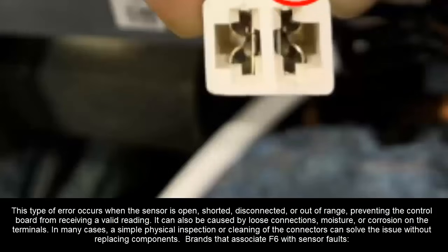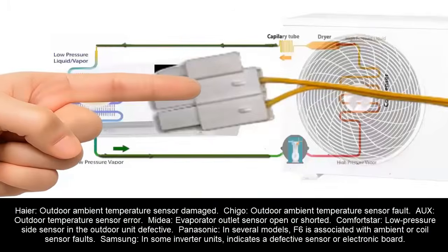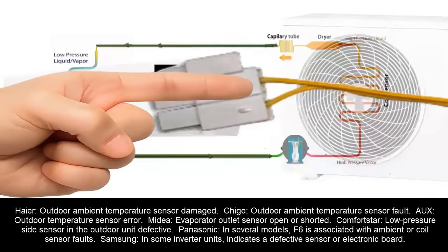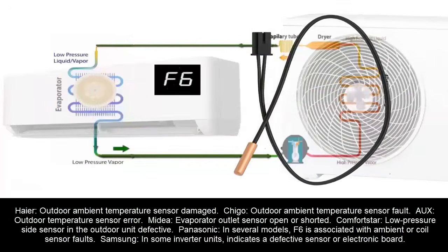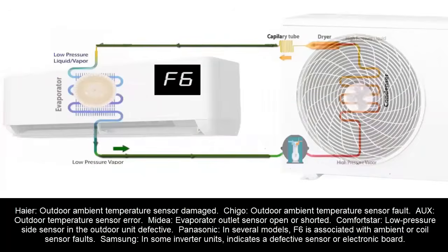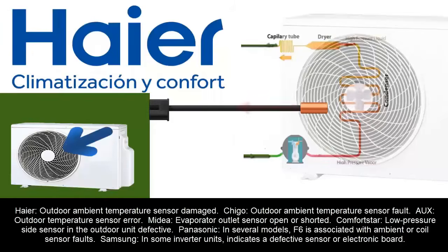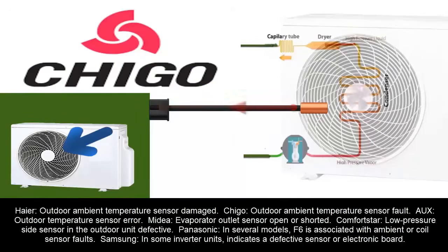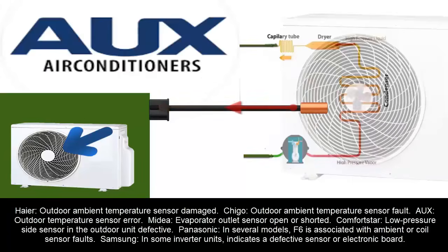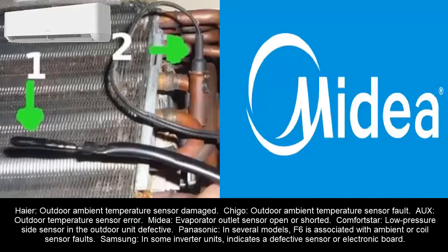Brands that associate F6 with sensor faults. Haier, outdoor ambient temperature sensor damaged. Chigo, outdoor ambient temperature sensor fault. AUX, outdoor temperature sensor error. Midea, evaporator outlet sensor open or shorted. Comfortstar, low pressure side sensor in the outdoor unit defective.